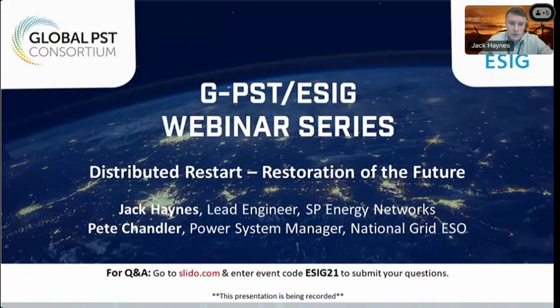A related question: did you have to modify the protection settings, particularly for the inverter, to cater for the high inrush current when energizing the transformer? Yes, we did. There was a protection assessment done by one of our teams prior to testing to make sure the protection settings would be sufficient. A lot of the issue was around there being enough fault current to trip the protection, but a detailed analysis was done to ensure the protection settings implemented for the trials were sufficient. We were lucky not to experience any faults during the trials, but we did experience a series of trips, predominantly on under voltage and under frequency, as a consequence of the inrush. We'll be making suggestions for protection amendments as part of the report.